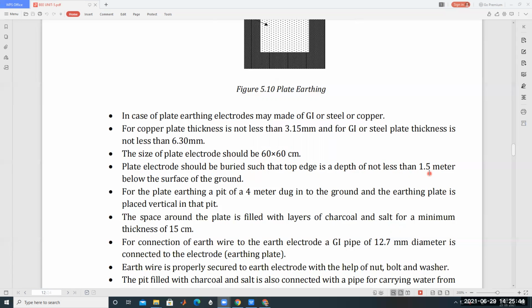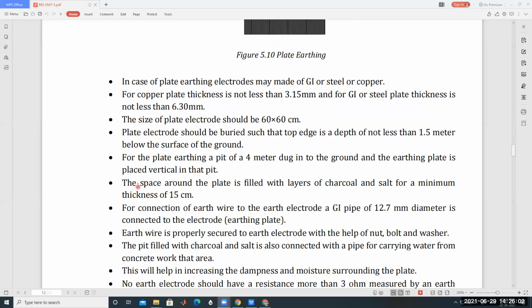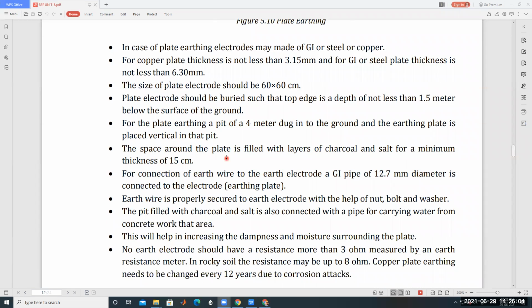For plate earthing, a pit of 4 meters is dug into the ground, and the earthing plate is placed vertically in that pit. The space around the plate is filled with layers of charcoal and salt with a minimum thickness of 15 centimeters.